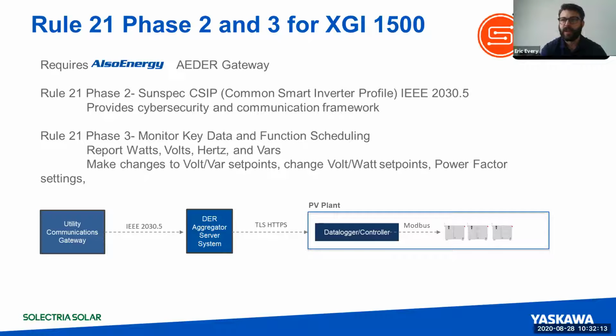And if they catch it in a window during that one second dip, then you've adjusted for something that only lasted a couple seconds. Once the transient passes, now you're in a worse position. You've fired a protection function, a voltage change you shouldn't have, and the voltage is way out of line.